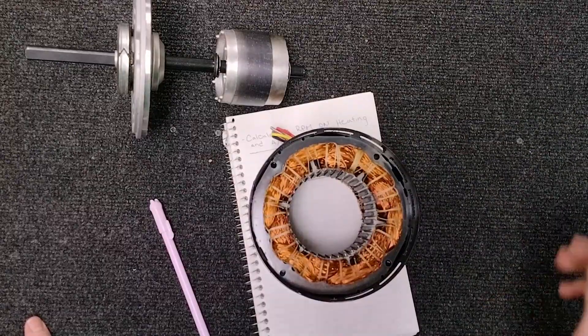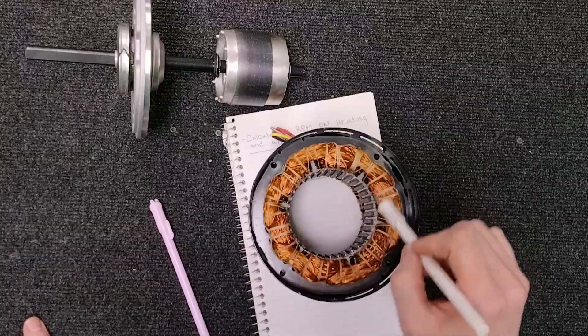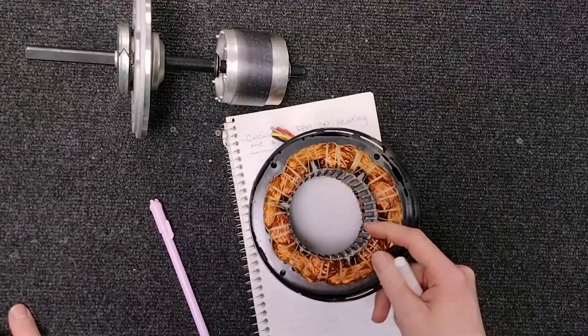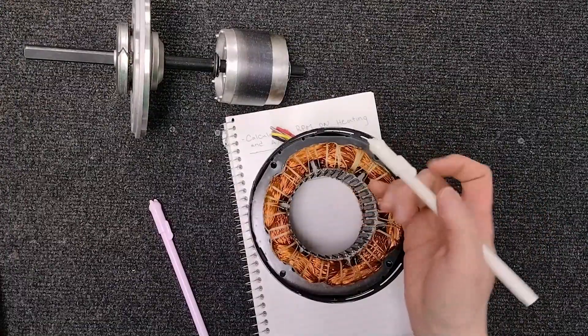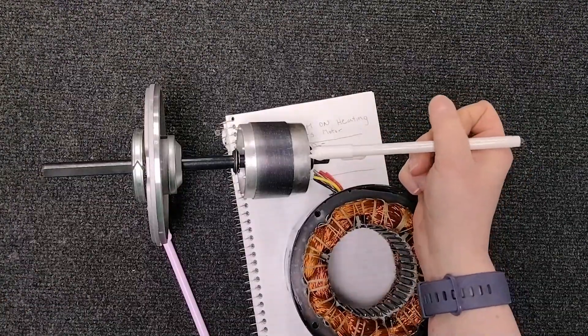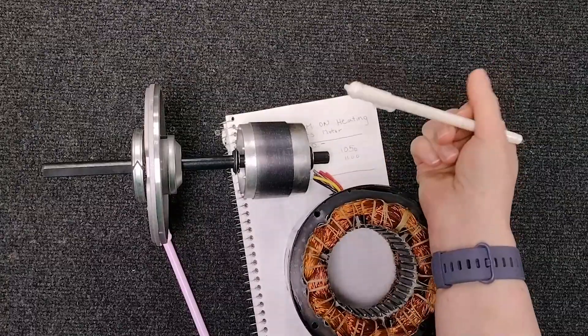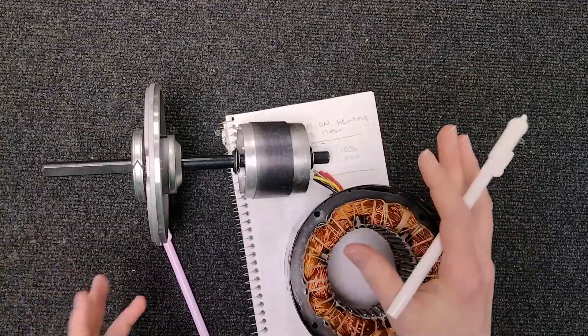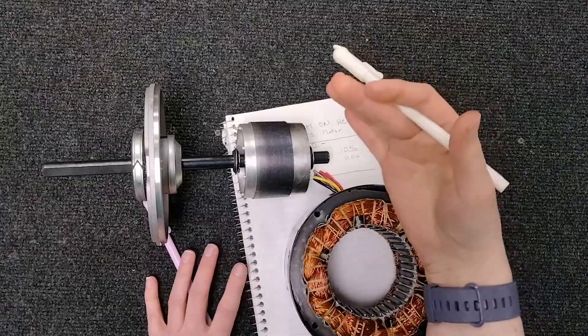Just a fun fact, the relationship between these poles and the RPM, which of course stands for rotations per minute, it has to do with the magnetic field which is produced in the stator poles. So this field here leads to the creation of magnetic fields in the rotor that actually relate to the frequency of the field in the stator. So when we say slip, what we're accounting for in that RPM is the difference between the stator's synchronous speed and the actual operating speed.